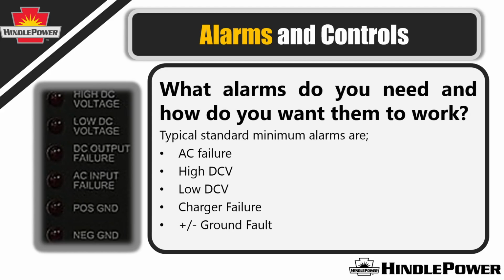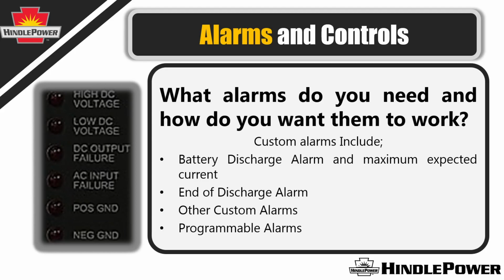So again, as I stated before, these are the standard typical minimum alarms that are going to be in a charger no matter what. So those are going to be in there almost automatically. But now you get into some of the more fancy, sophisticated alarms. You have a battery discharge alarm, which lets you know when the battery is actually putting out current. An important thing to know there is if you're going to put a battery discharge alarm in, it's actually measured through a shunt, so we need to know the maximum current of the load profile.